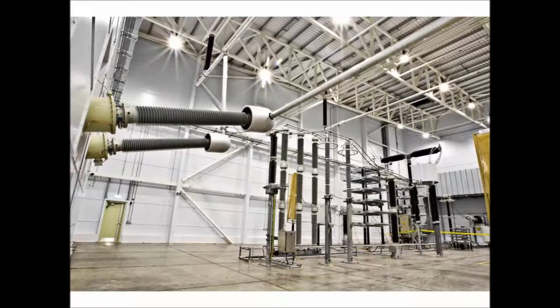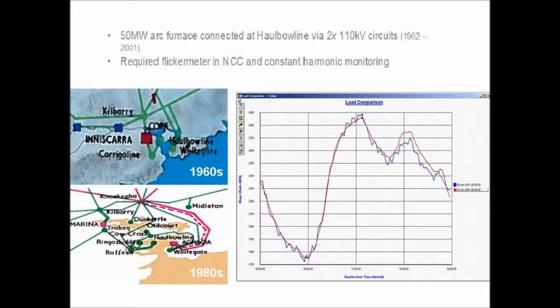And then inside we've got the filter banks for the 32nd and the 60th. So they're an 80 megavar filter and a 25 megavar filter, and they're there to block the higher order harmonics and shunt them to ground.